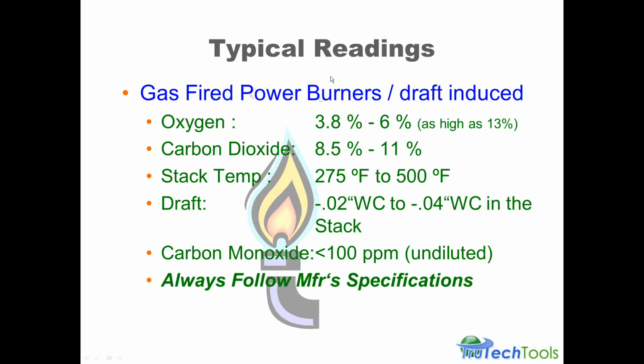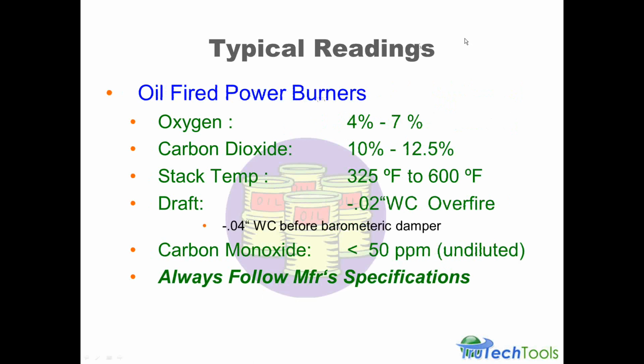And these are typical readings. Again, you need to refer to the manufacturer specs to get the exact numbers for the equipment you're working with. And in oil, the oil-fired power burners, 4 to 7% oxygen, carbon dioxide 10 to 12.5, and stack temperature 325 to 600, and the draft over fire 2/100ths and 4/100ths negative before the barometric damper, and less than 50 parts of CO undiluted.